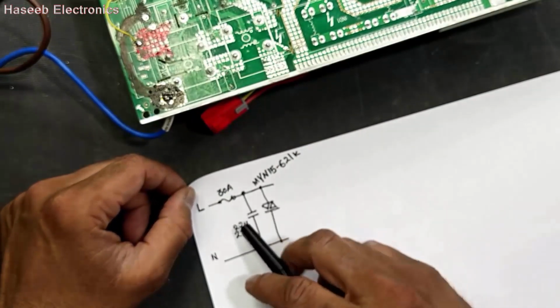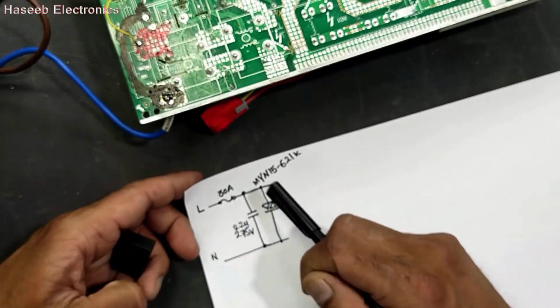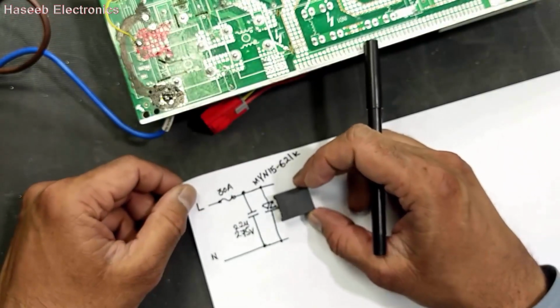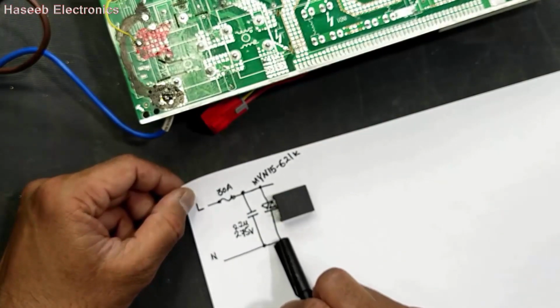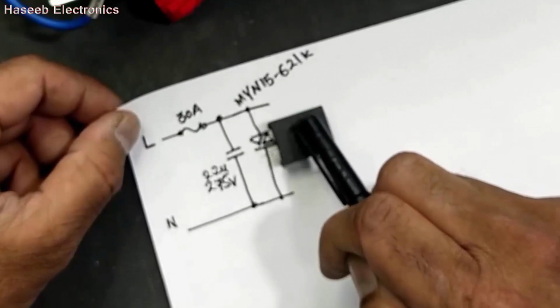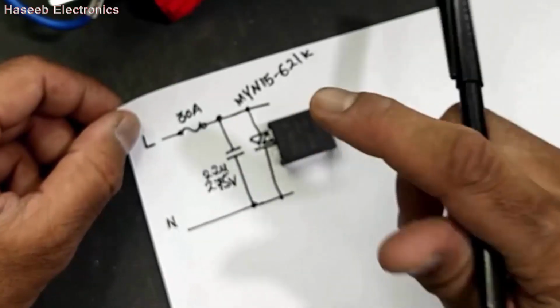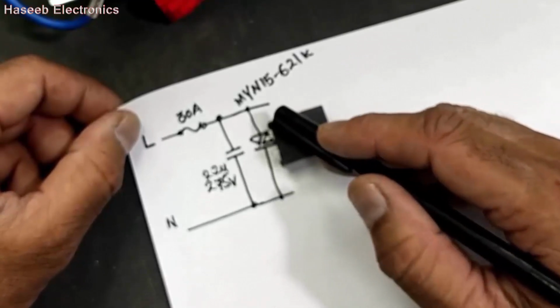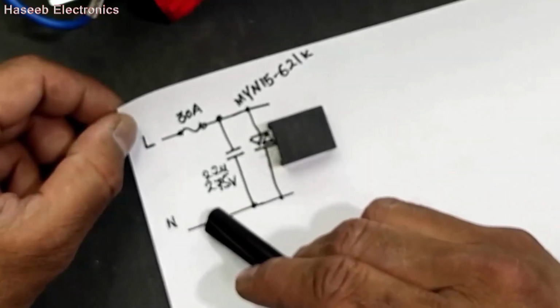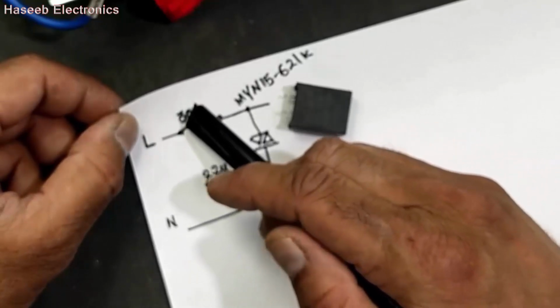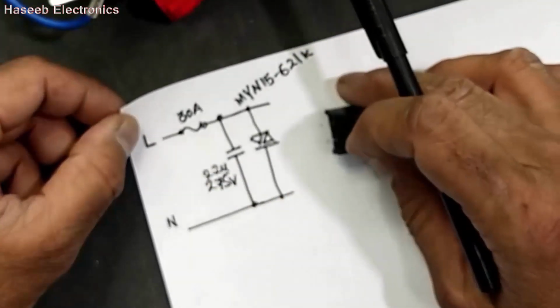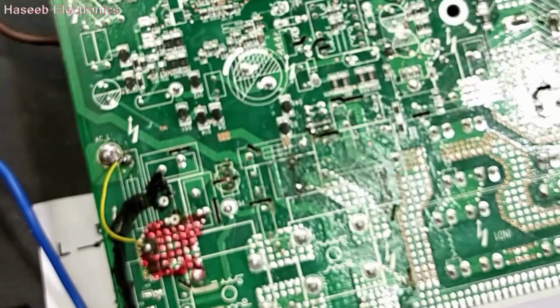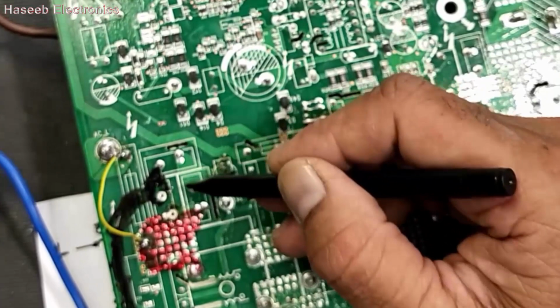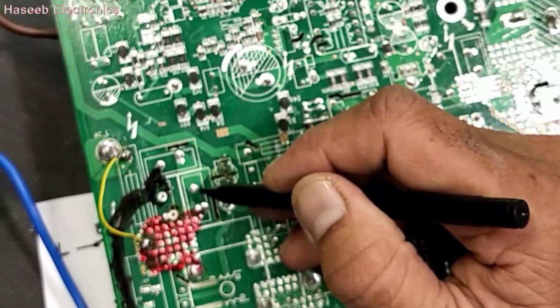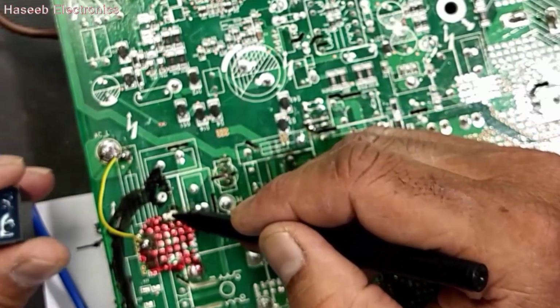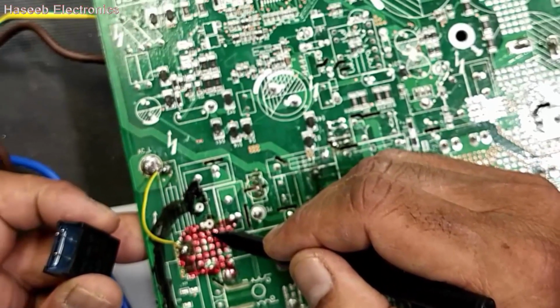The same is here. Here is high frequency, here is high voltage. So this component will be connected here. It is connected between line and neutral. At high voltage, more than 385 volt, it will become short internally. When it becomes short circuit internally, the current will flow in this path and the fuse will burn out. The next circuit will be protected. In the same point, one point is here, second point, so it is the same MOV, but in this configuration it is connected between line and neutral.